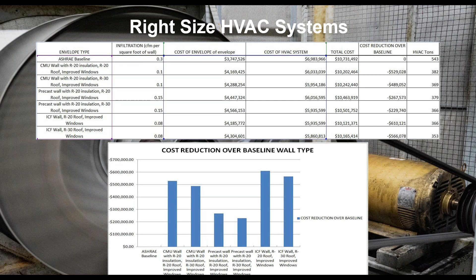Lo and behold, what we found was that the better envelope, ICF walls with an R20 roof and better quality windows, combined with the reduced HVAC tonnage we were able to achieve, was actually the least expensive first-cost option. That didn't even account for the reduced electrical load, the reduced lighting load, or the 30-year savings achieved across the life of the building. But it really drove home the fact that first cost savings can be achieved by building a high performance facility.